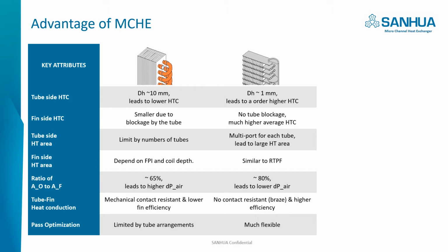At the tube side, the port microchannel is quite small, around 1 millimeter, so the tube side heat transfer coefficient is higher. At the air side, there's no tube blockage, and also the wavy fin has better heat transfer coefficient. And what's more, fin tube heat exchanger has this mechanical expansion, so there's contact thermal resistance. But for microchannel, it's all brazed, so there's no thermal contact resistance.